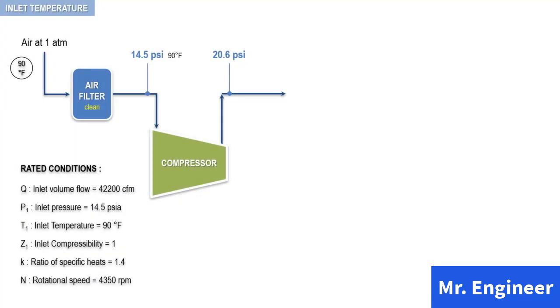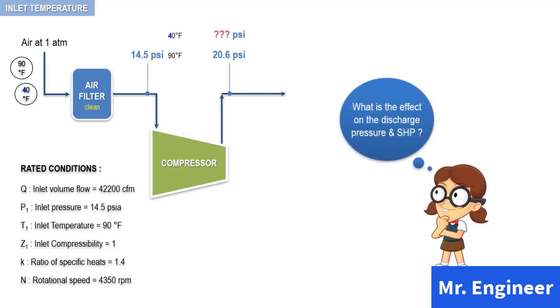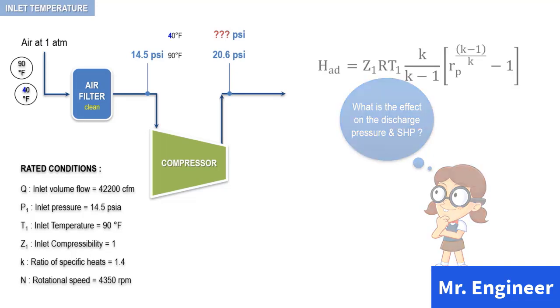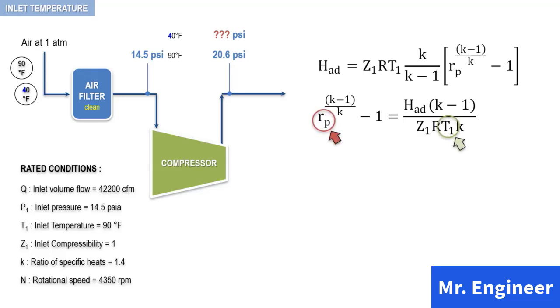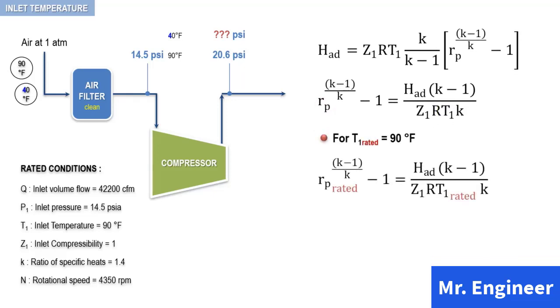In this video, we will examine the effects of a variation in inlet temperature. Let's assume that the inlet temperature drops from 90 degrees Fahrenheit to 40 degrees Fahrenheit, while other inlet conditions remain at rated values. What is the effect on discharge pressure and shaft horsepower at the rated inlet volume flow? Rearranging the adiabatic head equation yields the following in terms of pressure ratio. This equation indicates that a change in inlet temperature inversely affects the pressure ratio.